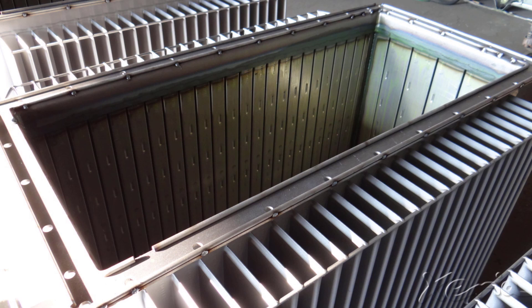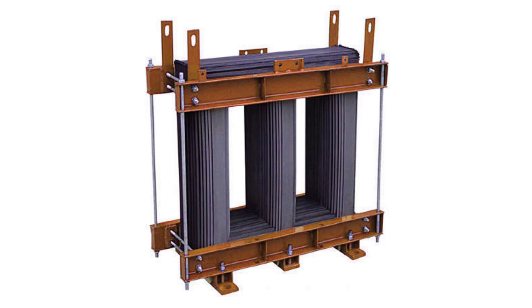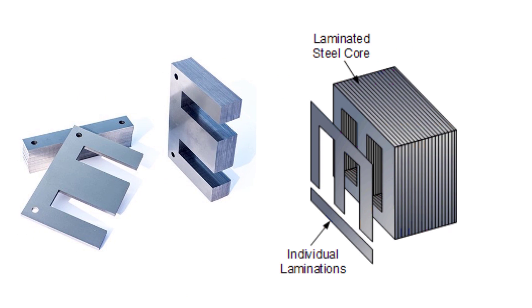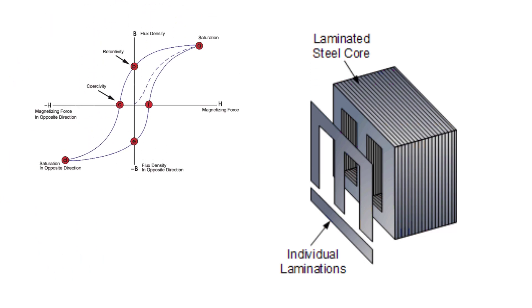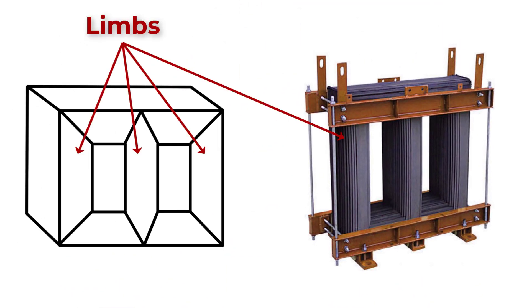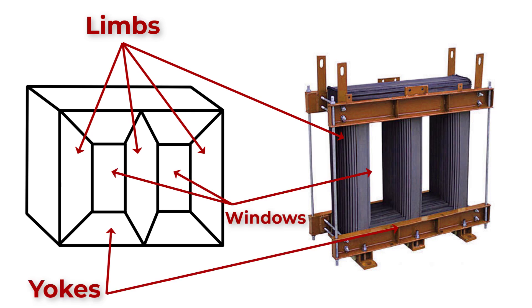Inside the tank there are the core and the windings. The core is the magnetic coupling between the primary and secondary windings by providing a low reluctance path for electromagnetic flux. The core is made by stacking thin sheets of silicon steel which are separated by thin insulating material. This arrangement ensures minimizing hysteresis losses, and eddy currents. The core consists of limbs which carry the primary and secondary windings, and these limbs are magnetically coupled.